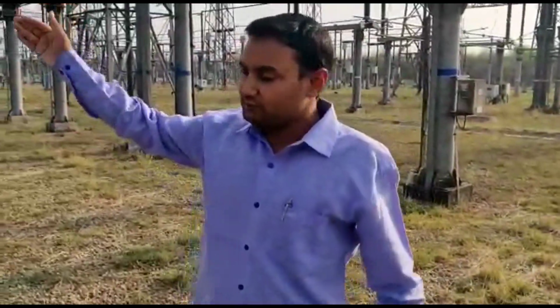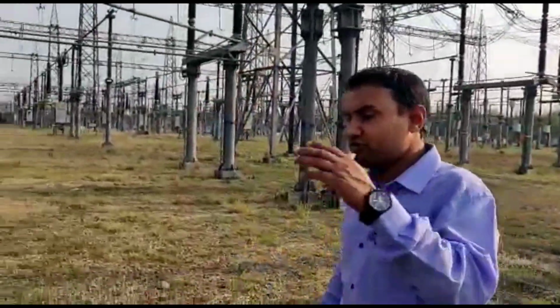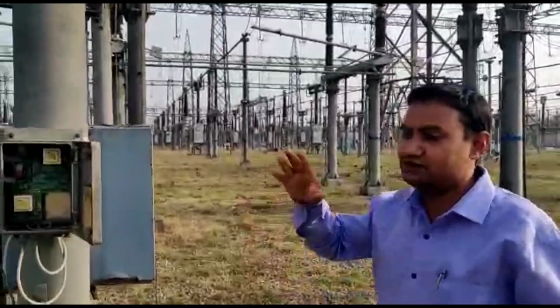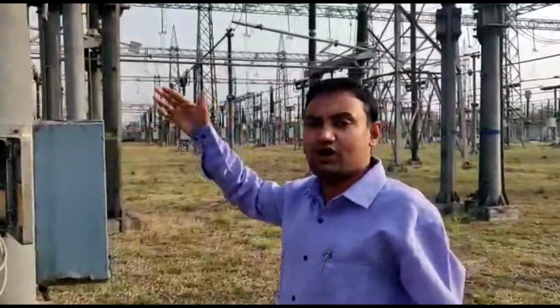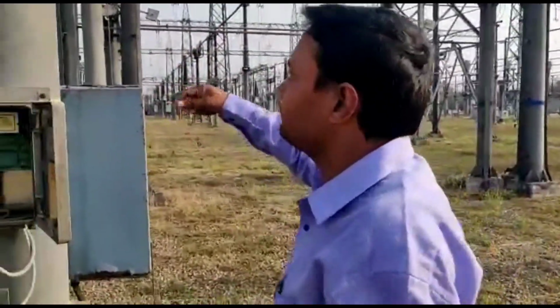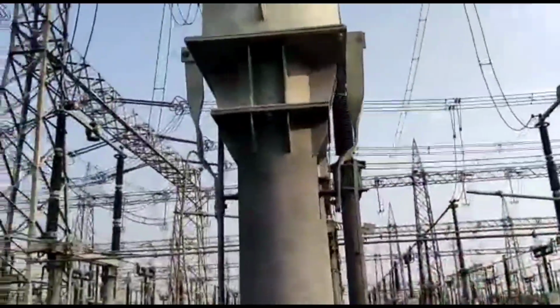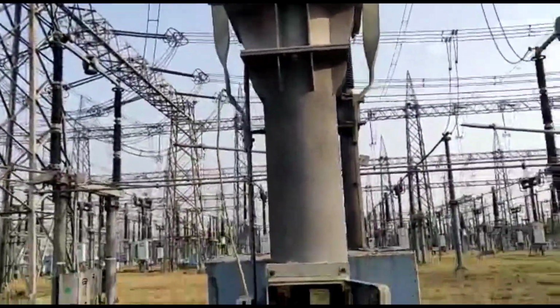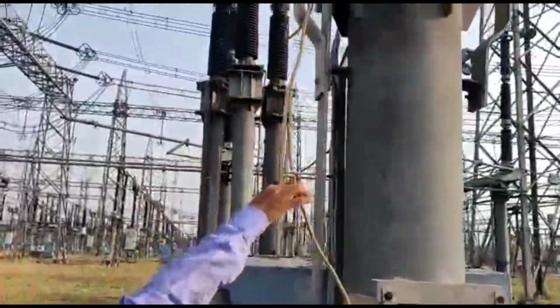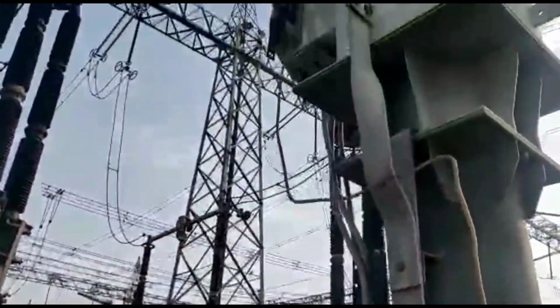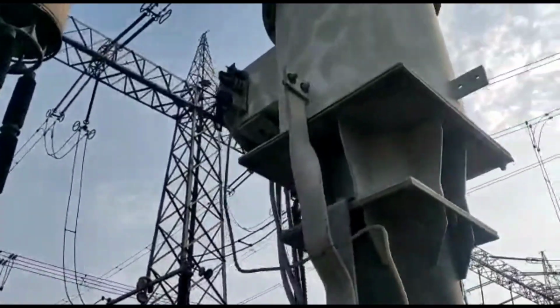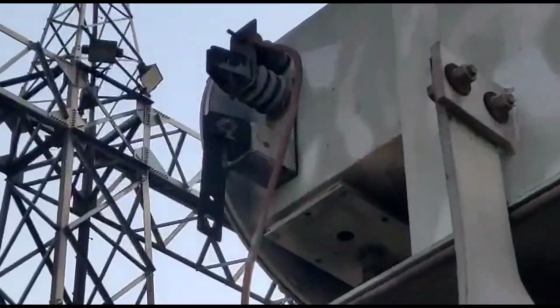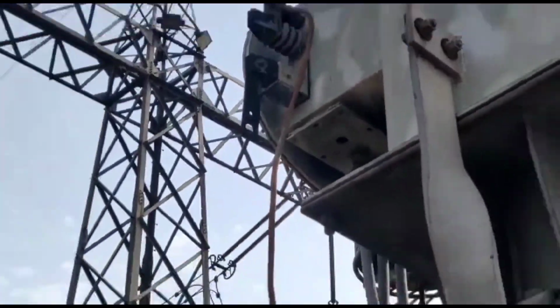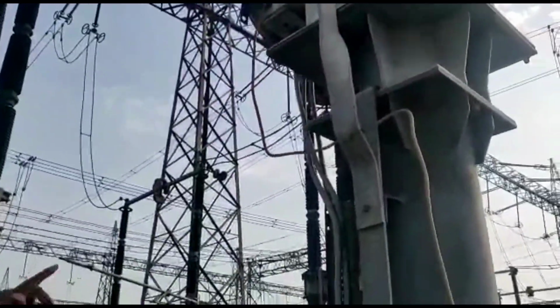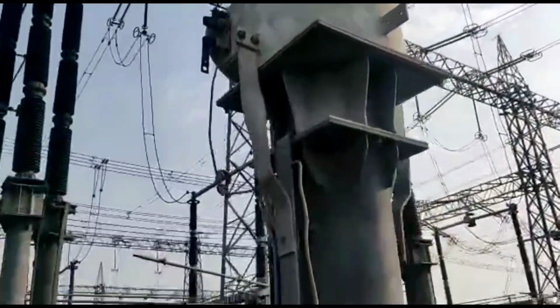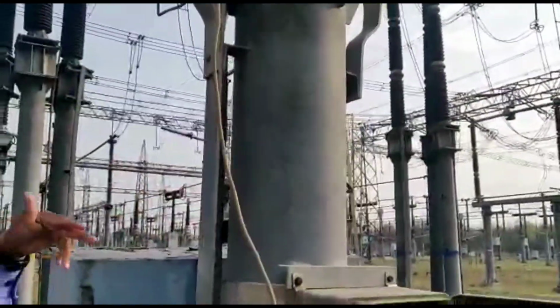Now again coming to this CVT. You know that the high frequency signals are transferred from this CVT to the other end. Now how is this done? Basically, if you see here, one wire is coming from the CVT top end, and this other wire is connected to the CVT bottom point, and inside there is a terminal called the HF terminal or high frequency terminal. From that high frequency terminal, you can directly connect this wire to your PLCC equipment.